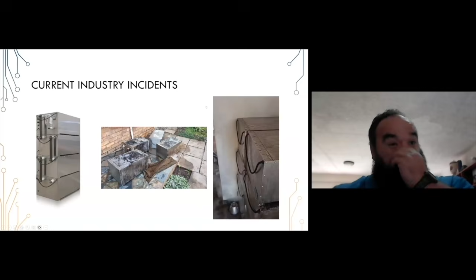Looking at a current incident in the industry, we've got a battery that went into thermal runaway. An incorrect voltage was put over to a cell. It was incorrectly wired, which is an error, but it did short out the BMS, or the BMS did not function correctly. In essence, the electrician who disconnected here ended up in a coma in a hospital.